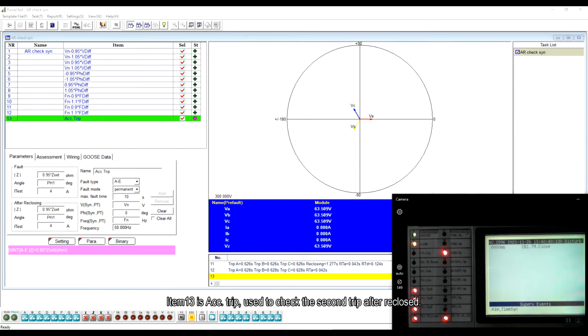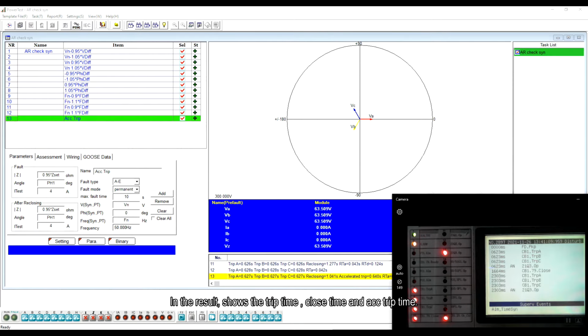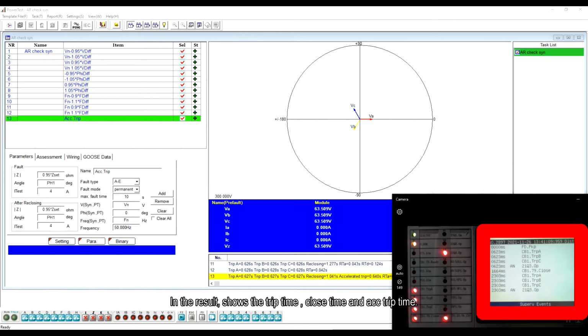Item 13 is Acc. trip, used to check the second trip after reclosed. In the result showed the trip time, close time, and the ACC trip time. On the relay's screen, it shows the trip, reclose, trip sequence information.